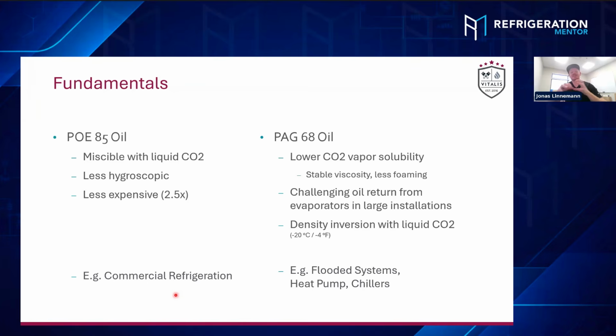So the PAG oil doesn't like CO2 that much, so it doesn't dissolve that much CO2 vapor, which makes it more stable over the different operating conditions. Like the viscosity is very stable. That also leads to less foaming, which is pretty nice in the compressor because the foaming will always multiply the oil carryover of the compressor itself. But the other part of that is it's way more challenging to handle that oil in a normal oil return because it's separating from the liquid. So you will sometimes have trapped PAG oil inside the liquid lines.